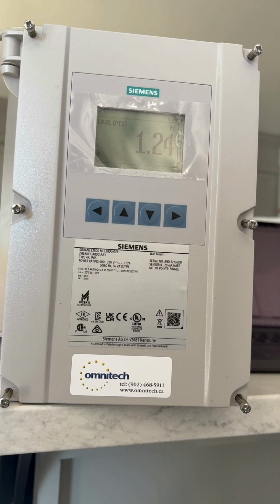This is a demonstration video on a Siemens LT500 controller with a milliamp input, along with a Siemens LH100 with a custom range of 0 to 12 feet of H2O. The LH100 is a hydrostatic, submersible pressure transmitter, for an application where we have a 12-foot tank. At 11 feet, we want a relay to activate so that we can turn on a solenoid for a valve.